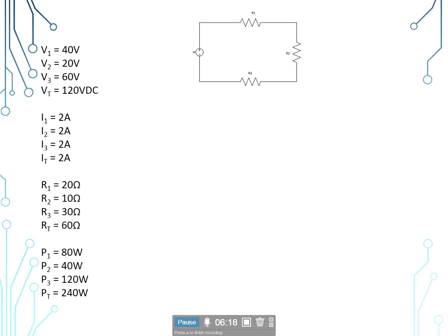So this is all the calculations that we can find for this particular circuit. We're ready to go out and make our live readings of this circuit and compare them to this and see if it's close, real close, and we're good to go in that part of the circuit. If we're way out of the ballpark, we need to look a little bit closer at that component or that part of the circuit because we have an issue there.